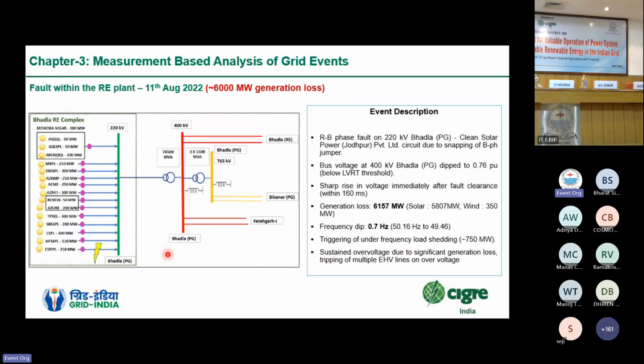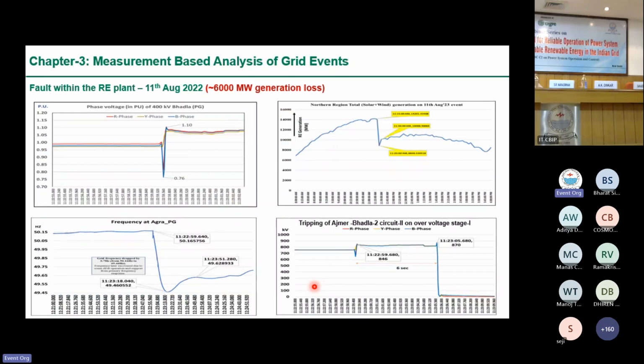During this fault, the voltage went down to 0.76 per unit. This is below the LVRT threshold. Then immediately after the fault clearance, we witnessed very high voltages in the grid, and subsequently we lost around 6,000 megawatt of generation, which led to a frequency dip of around 0.7 hertz. If we go into the details, this is the fault that took place. The fault was cleared within the specified time.